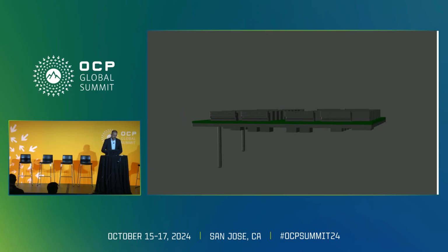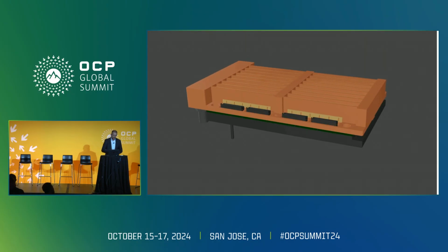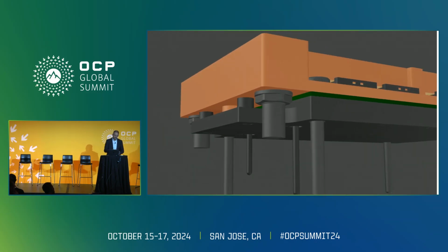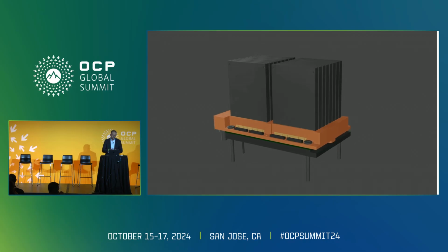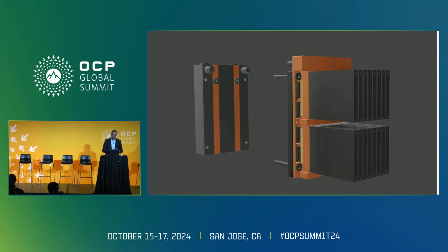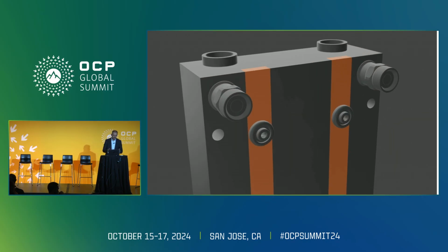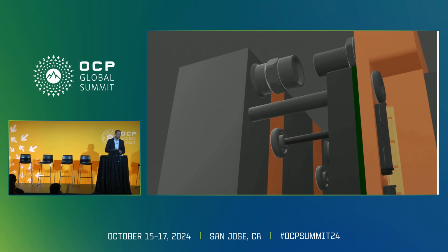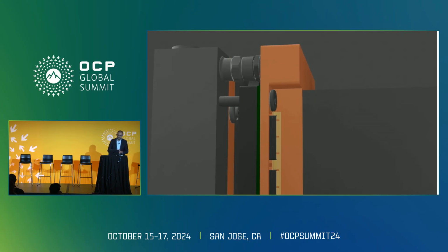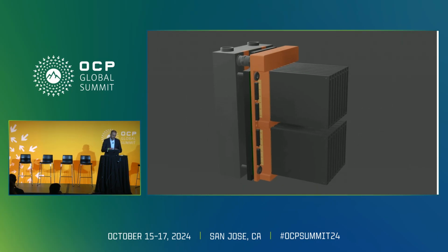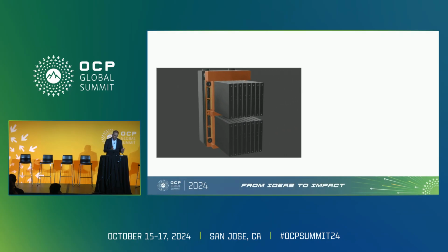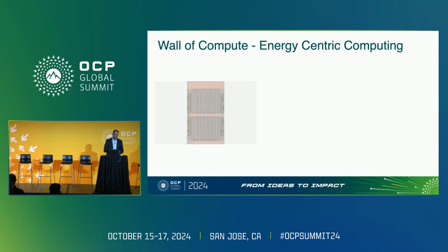Putting that back together, it reassembles the water jacket. You'll see the power pins and the water inlet. This module then plugs into a wall. This is one small section of the wall carrying the water and the power, 48 volts, and the module blind mates into the wall. You will see this module is one individual module in one slot of the wall.